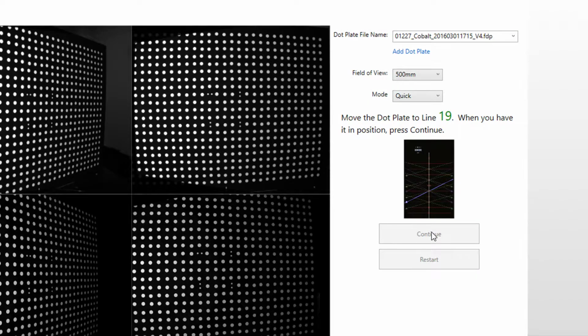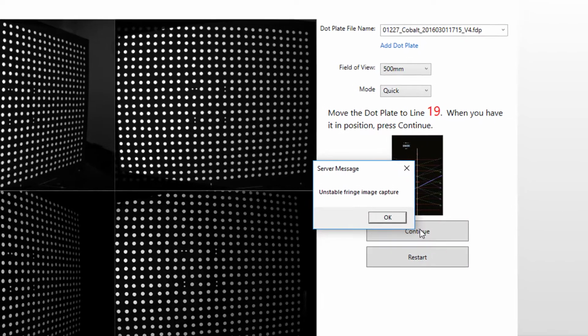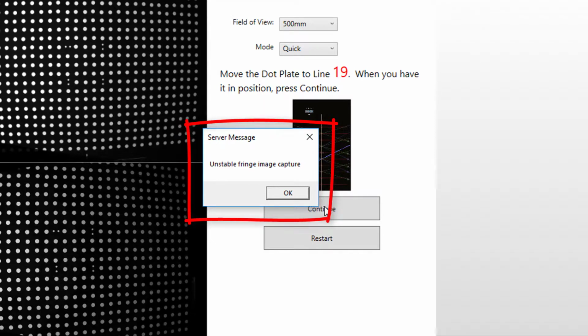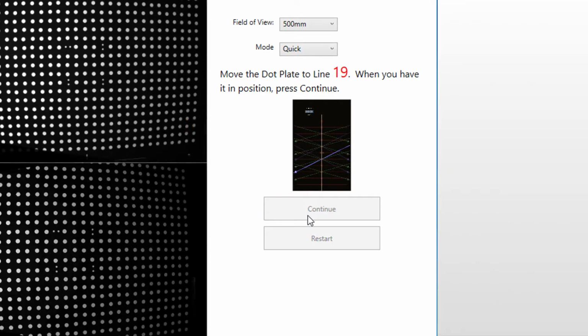If at any point in time the message Unstable Fringe Image Capture appears, make sure that neither the Cobalt nor the dot plate are moving and that nothing is moving near the back side of the dot plate. Any physical movement in the dot plate or the Cobalt, or any movement sensed by the camera behind the calibration dot plate, can be interpreted as movement during the scans. If this occurs, click OK, and then click Continue to take another scan at the same position. Do not move the calibration plate until that particular step has been completed.